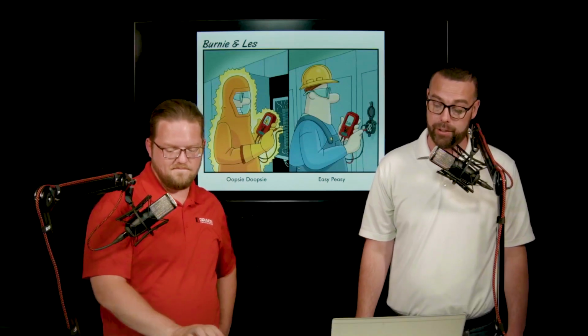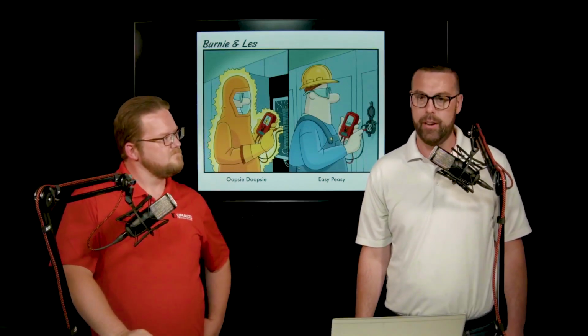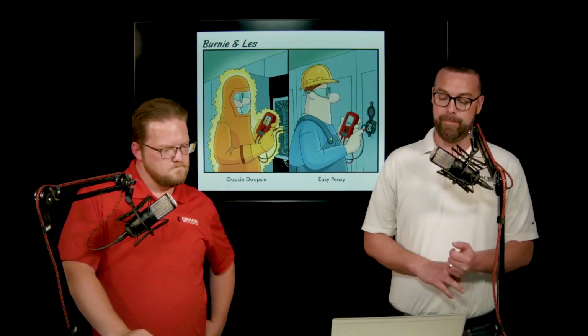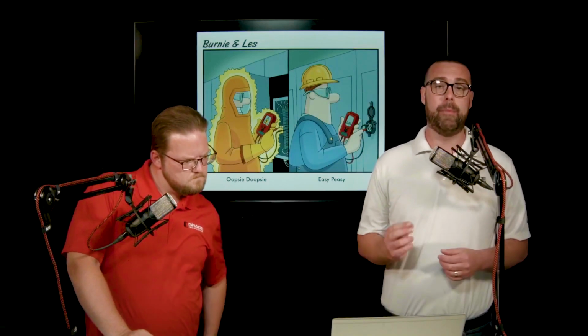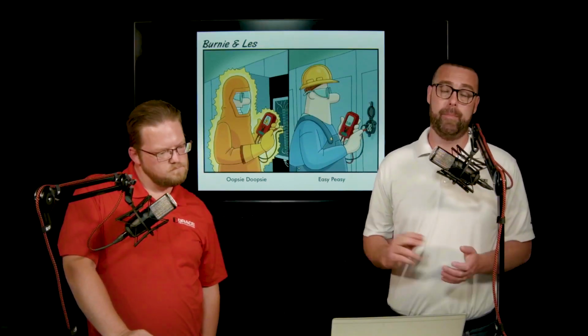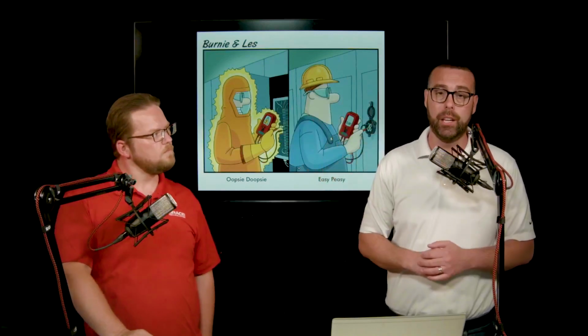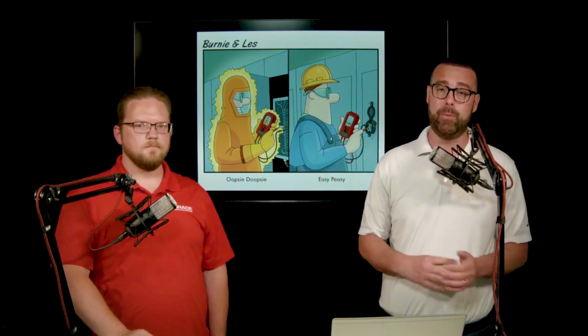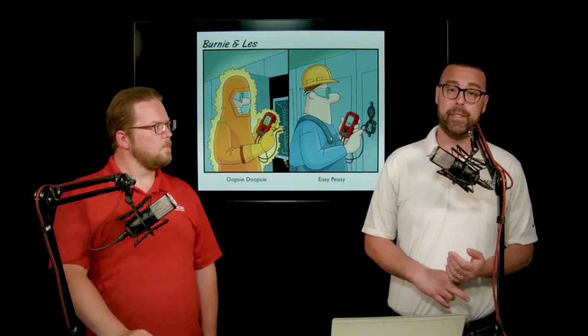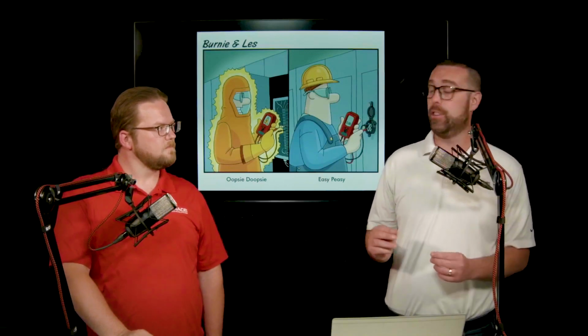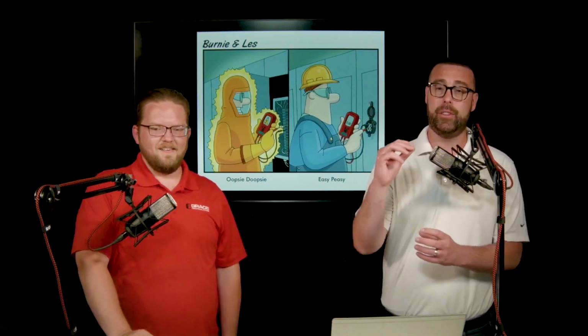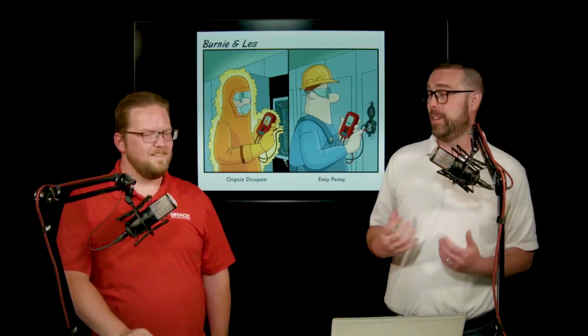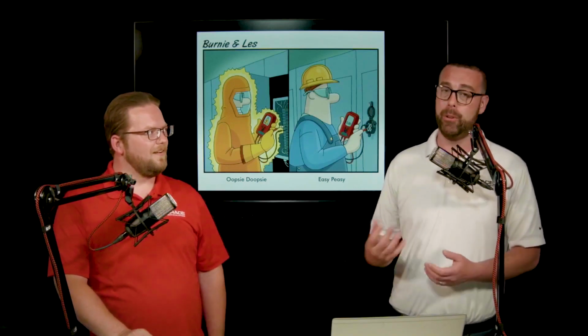Do you have any safety arc flash PESDs for overhead lines going to a manufacturer, a transformer? Got it, so that's a tough question, and it's actually come up in a multitude of different applications. The power lines, the power coming off the incoming utility, is generally a higher voltage than what we see with our low voltage permanent electrical safety devices. We've looked at trying to leverage our medium voltage indicator, however that's generally used in switchgear, as it's a direct half-inch bolt connection directly into the gear itself. I haven't had a real successful way to include some of those permanent electrical safety devices there.